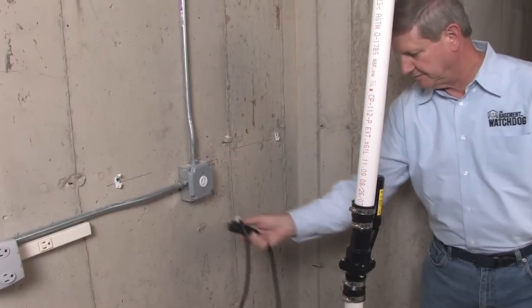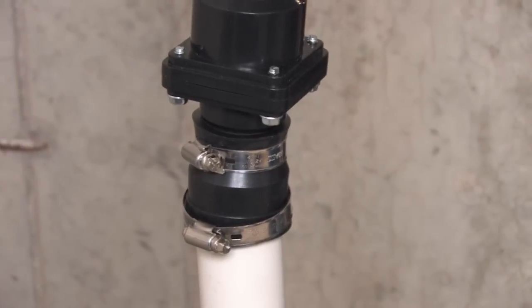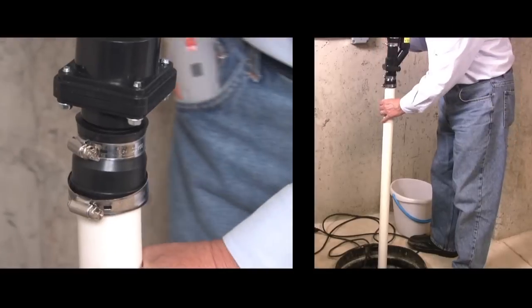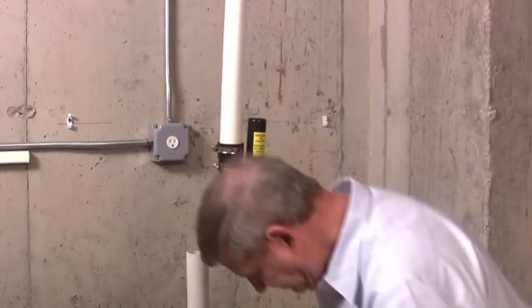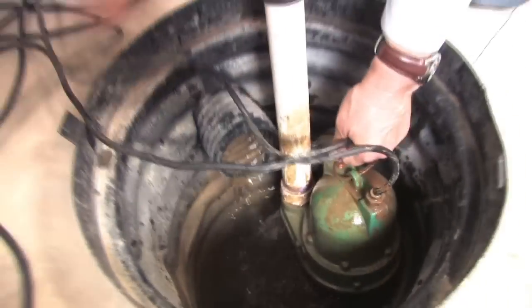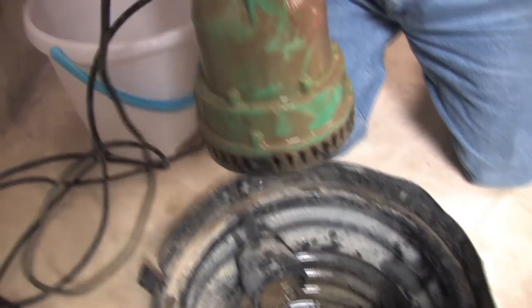Unplug the unit from the wall. Release the pump from the discharge pipe by loosening the hose clamp on the check valve or rubber union. Slowly remove the pump, as there will be water in the pipe above the check valve. Then remove the pump and pipe from the sump pit and place it in a bucket to contain any water left in the pump.